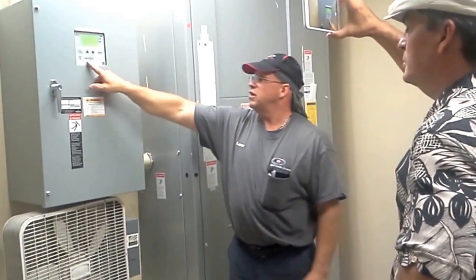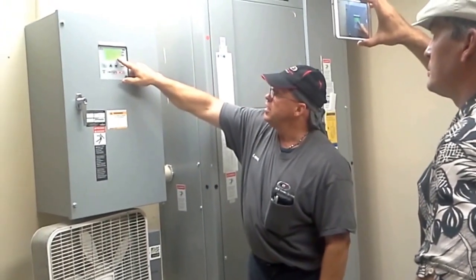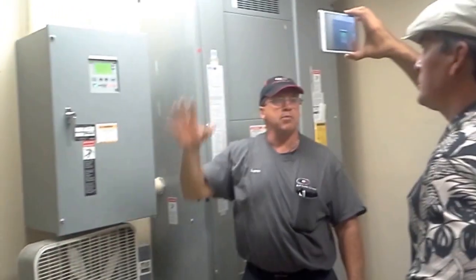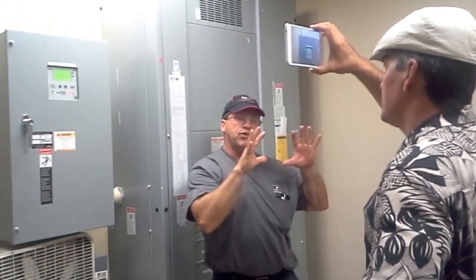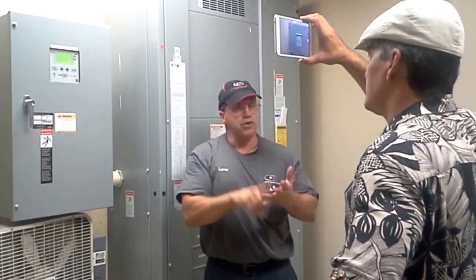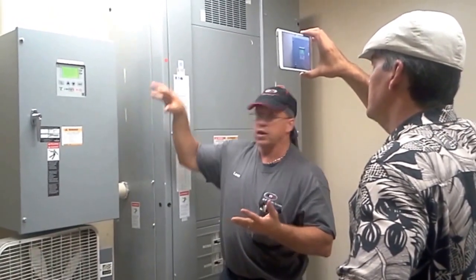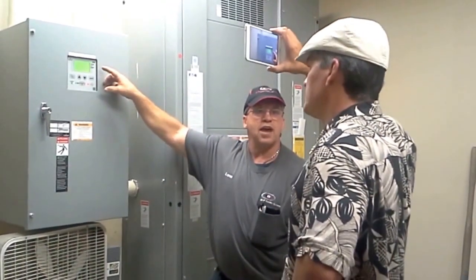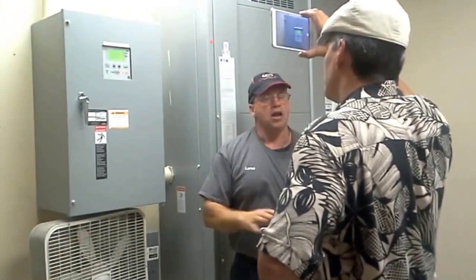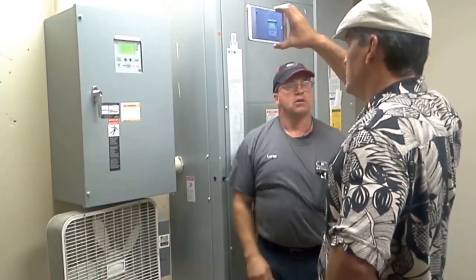Okay, let's say the utility came back. Look at that. My utility came back, right? But why did it switch back? Well, if you look up here, it's counting down. Emergency to normal, 10 minutes. It's going to verify that. It's going to watch that for 10 consecutive minutes, never missing a second. And you're going to have the right volts, frequency, all hertz, all your correct parameters for 10 minutes. Once I have that for 10 minutes, it's going to say, okay, 10 minutes has passed. Go ahead, switch over to utility.